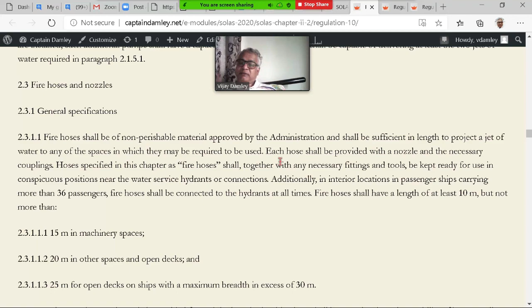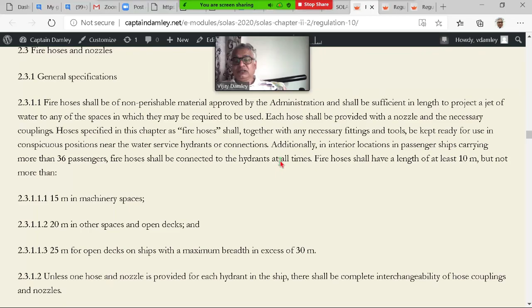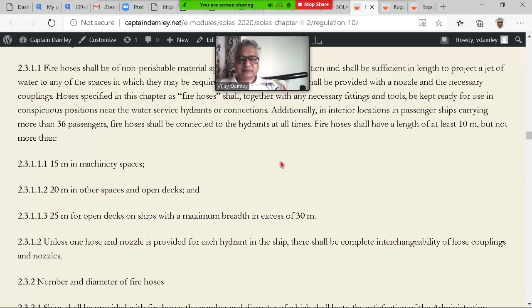If your ship is less than 30 meters, you can have 20 meters on deck and 15 meters in machinery space. Now, this is the maximum, but the minimum is 10 meters. Minimum is 10 meters and maximum is 15, 20, 25. This means your fire hoses on the ship should have some sort of coding, so after the fire drill you don't mix them up. That is why normally around the couplings we use color codes. If it is cream color, it is from the engine room. Blue means it is from accommodation, and some other color says it is from elsewhere. Normally the fire hoses inside the accommodation are thinner ones, 40 millimeter size. Otherwise they are 65 millimeters.